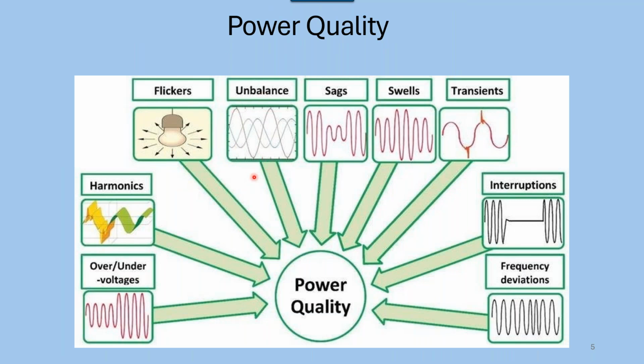Unbalance is a real problem with power quality. People don't realize it, and I had 2 plants side by side. One had all kinds of motors burning up, the other didn't. It turned out it was unbalance. If you have unbalance, you're going to have voltage between these 2 phases, and bottom line, that causes what we call negative sequence current, which is running the wrong direction, which is not a good thing. And I'll talk more about that.